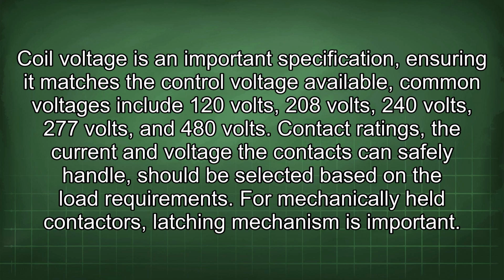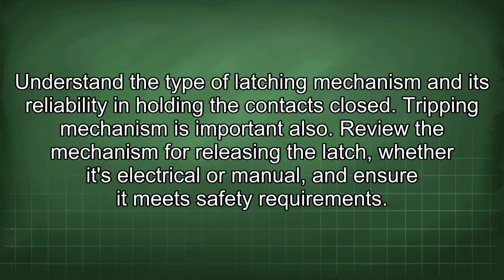For mechanically held contactors, the latching mechanism is important. Understand the type of latching mechanism and its reliability in holding the contacts closed. The tripping mechanism is important also. Review the mechanism for releasing the latch, whether it's electrical or manual, and ensure it meets safety requirements.